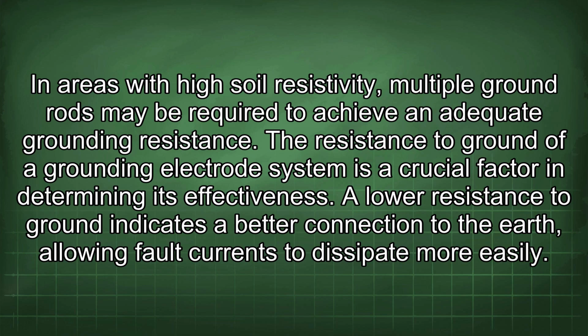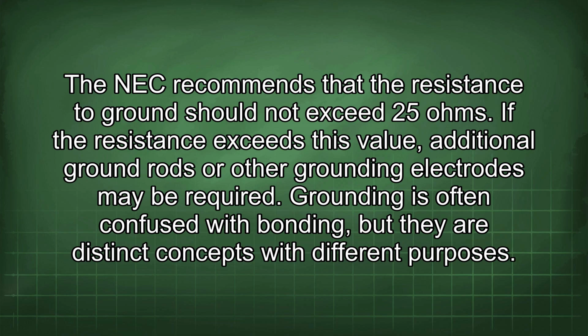The resistance to ground of a grounding electrode system is a crucial factor in determining its effectiveness. A lower resistance to ground indicates a better connection to the earth, allowing fault currents to dissipate more easily. The NEC recommends that the resistance to ground should not exceed 25 ohms. If the resistance exceeds this value, additional ground rods or other grounding electrodes may be required.